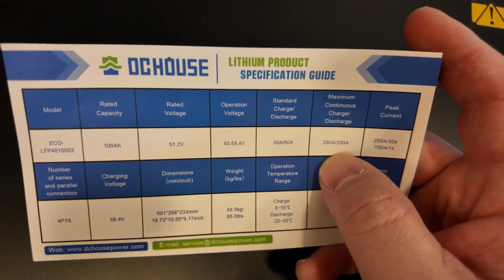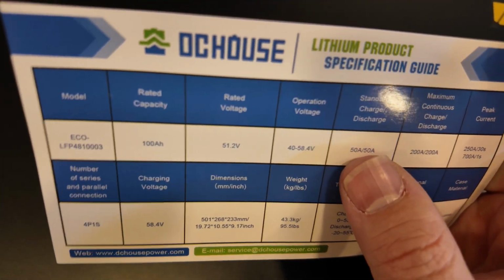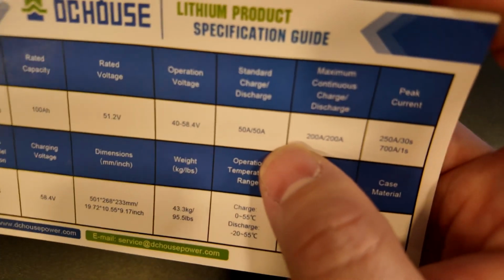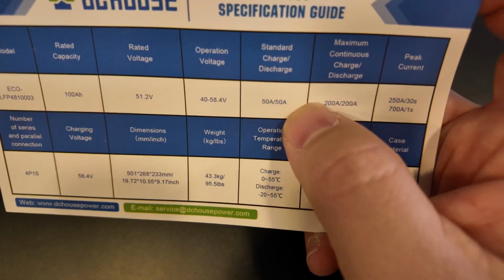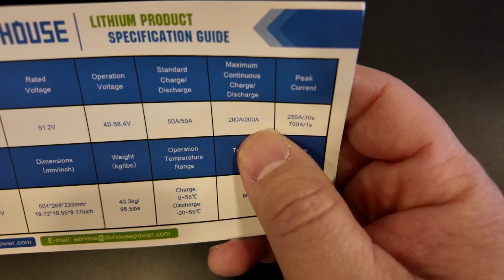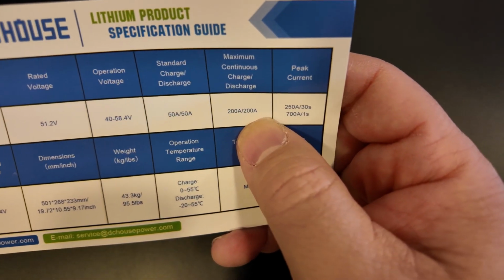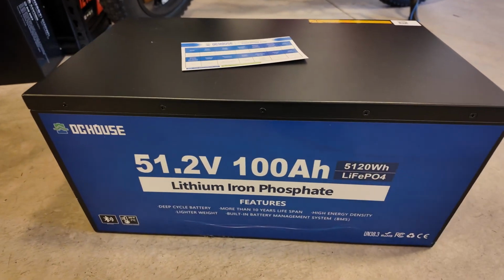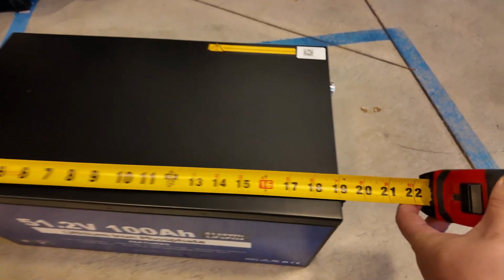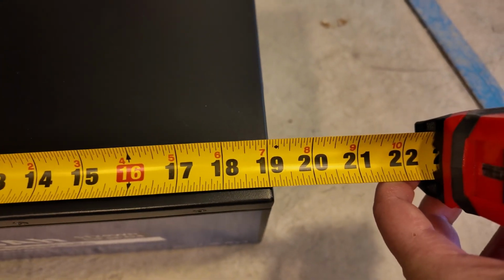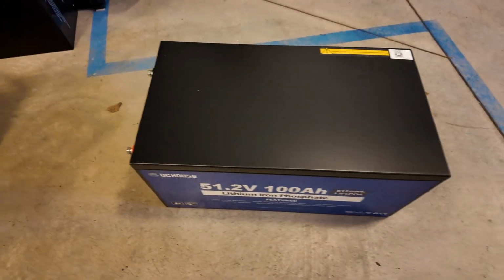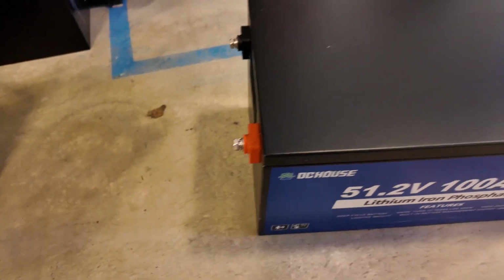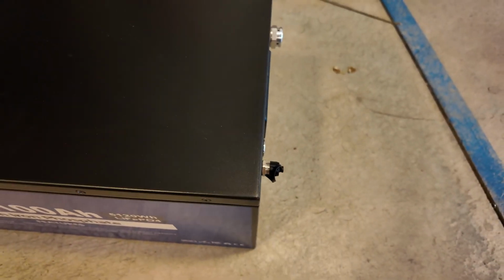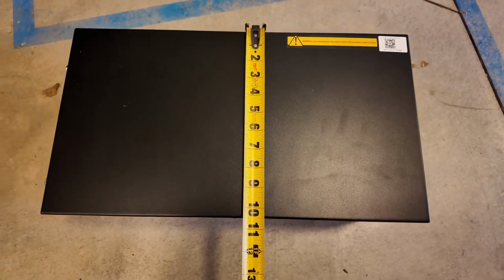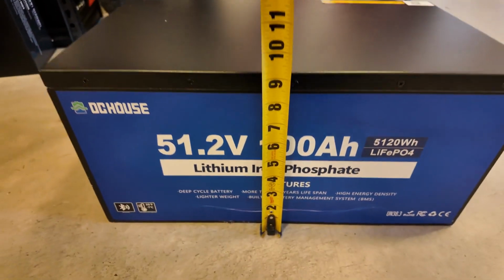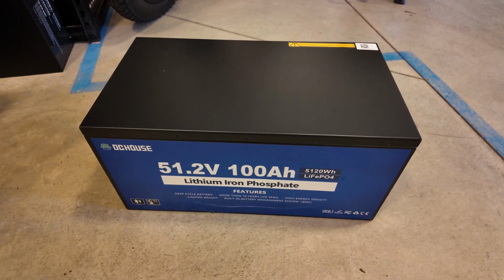In terms of specifications, this is a 100 amp hour, 51.2 volt battery. The recommended charge and discharge rate is 50 amps, with a maximum continuous rate of up to 200, which is pretty standard for a golf cart style battery like this. In terms of dimensions, the case is approximately 19 inches long, though you'd want to add about 2.5 inches to factor in the protrusion of the terminals, the screen port, and the vent. It's approximately 10.5 inches in depth and approximately 9.25 inches tall, and it weighs in at just about 100 pounds.